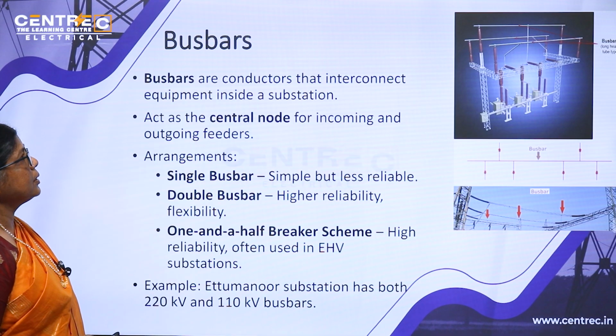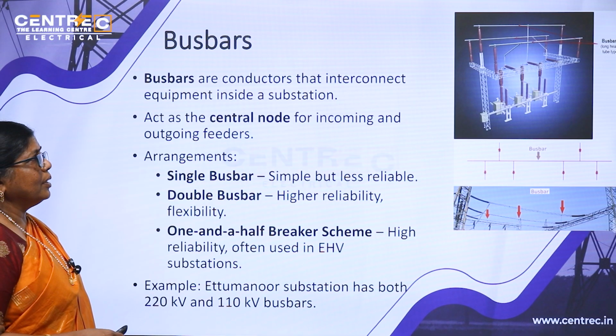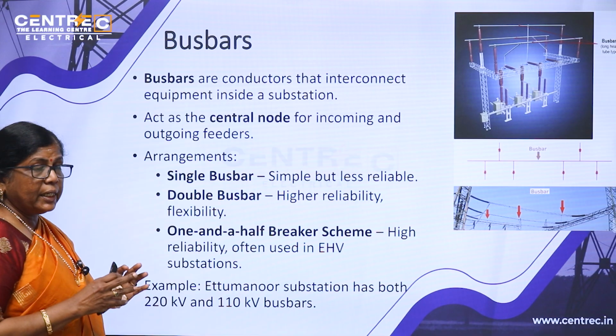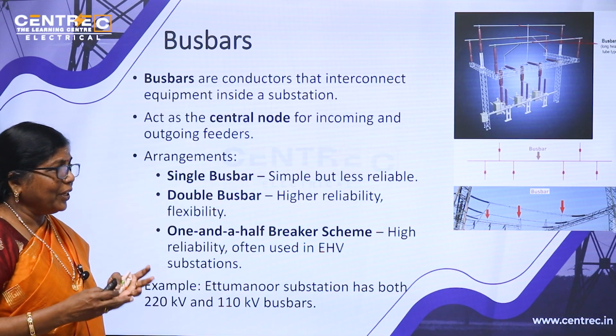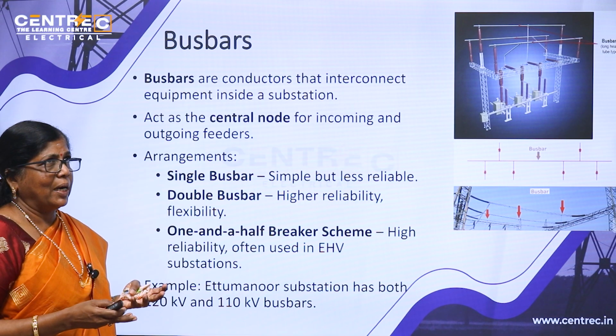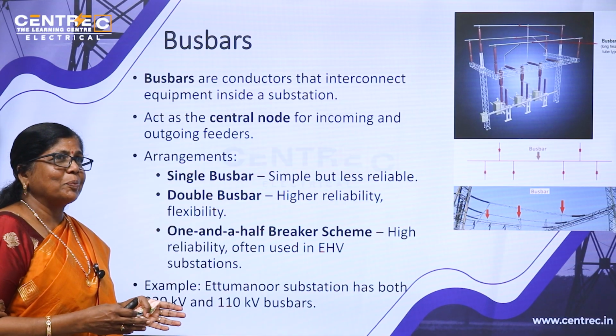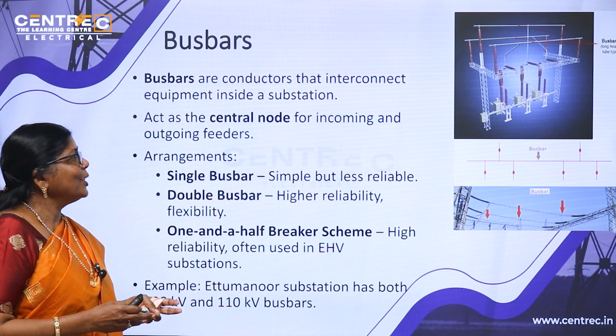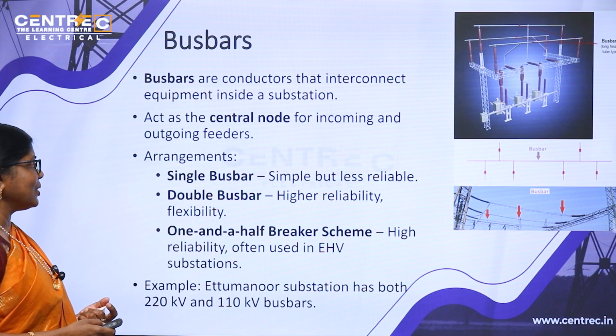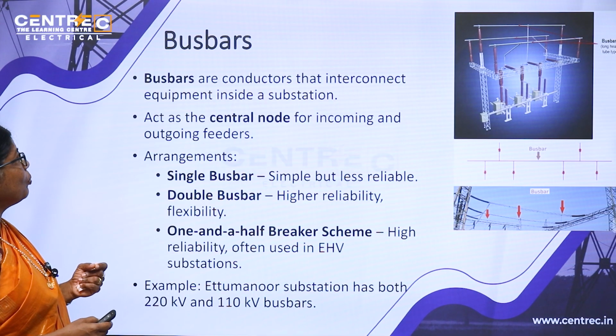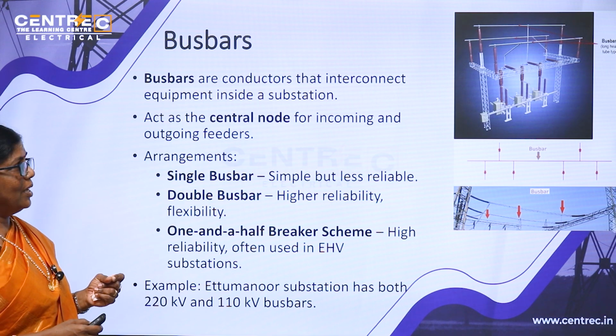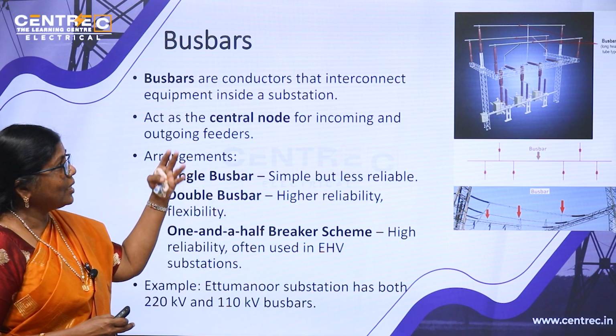Then bus bars. First of all, we have no idea about what a bus bar is. Different sections have mentioned bus bars. In a panel board also we have bus bars. In a substation we have bus bars. So what actually are bus bars? They are conductors that interconnect equipment inside a substation. That is mentioned about the large size bus bars.